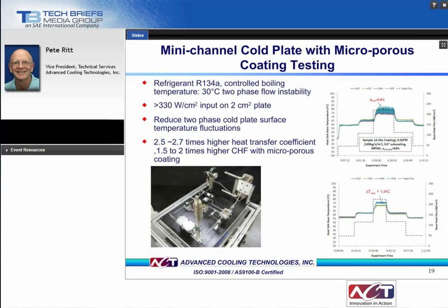The top graph shows the system without microporous coating. Temperature variation in the highest heat flux region in the center was measured to be 5.8 degrees C. The graph on the lower right shows the identical setup, but with a porous coating applied to the microchannel area. As can be seen, the temperature variation in the hottest heat flux section was reduced to 1.4 degrees C. In addition, the microporous coating produced a significantly higher heat transfer coefficient and a significantly higher critical heat flux compared to the non-coated sample. Microporous coating of mini channels in the evaporator area is a method to improve performance of pumped two-phase systems.